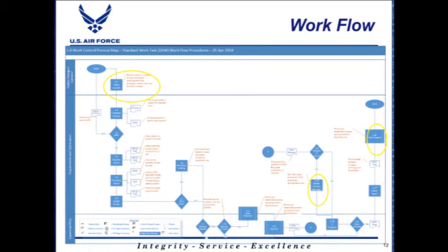Now, another example is ceiling leaking. Make sure that you know that if you have a ceiling leaking, that can be 3 different sources. That can indicate a roof leak, an HVAC return line, or it could even indicate a plumbing line. So if there's access to the ceiling and it's under 10 foot, poke your head around in there with a flashlight and try to see what it might be. Because if they have to assign it to one shop, the shop goes out. If the shop doesn't share that and say, yeah, it's not ours, then the process starts over. And it could be an endless loop that gets very frustrating. So as far as workflow, I just want you to understand that that's where a lot of stuff gets bottlenecked.